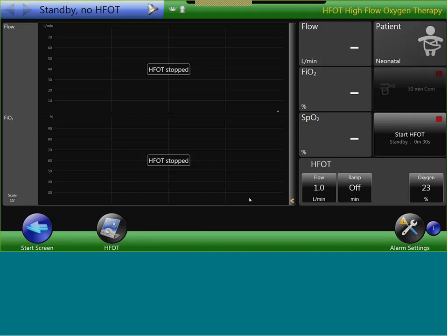So we would be inside the range of the uncertainty, even with these settings. But of course, if you set a PEEP of 5.8, that PEEP might not necessarily be exact at that point. That's true, but therefore we have the uncertainty, which is explained in the user manual.